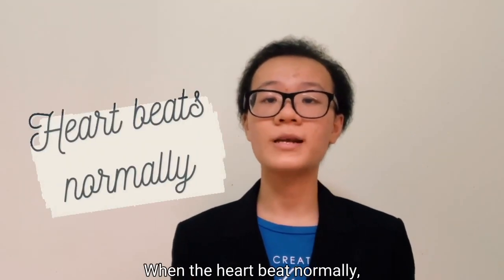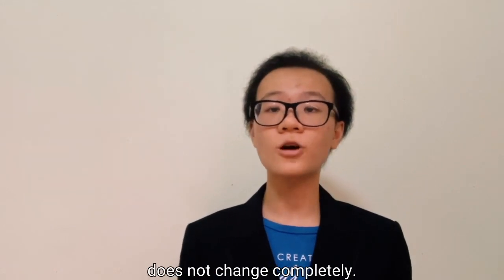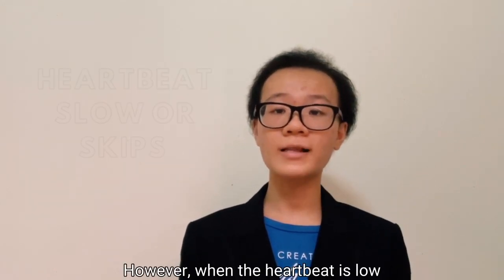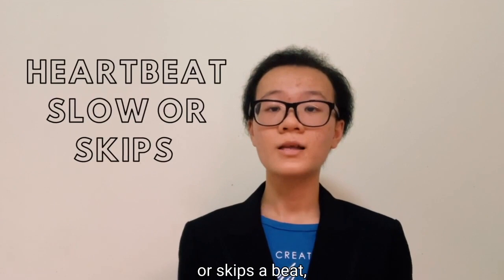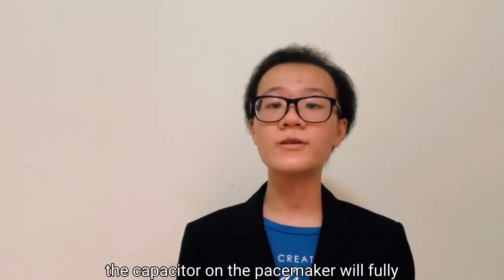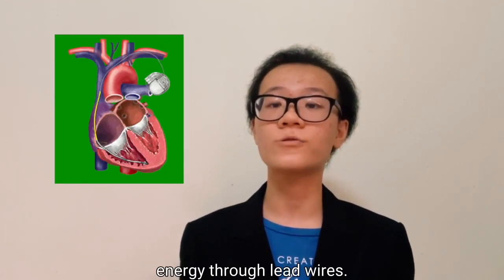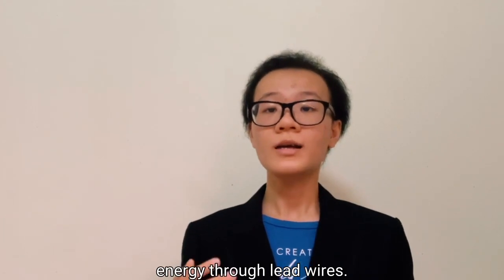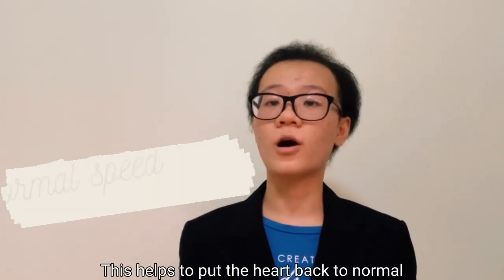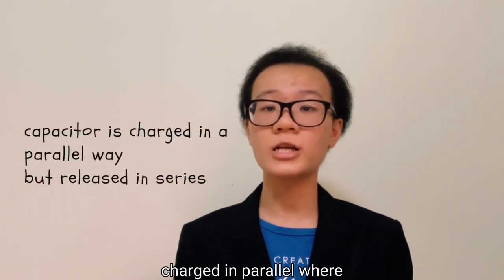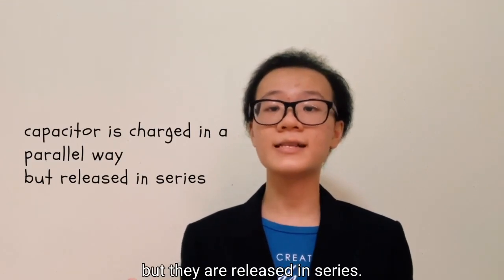When the heart beats normally, the capacitor of the pacemaker does not discharge completely. However, when the heartbeat is low or skips a beat, the capacitor on the pacemaker will fully charge and release the stored energy through lead wires. This helps to put the heart back to normal speed. The capacitors are actually charged in a parallel way, but they are released in series.